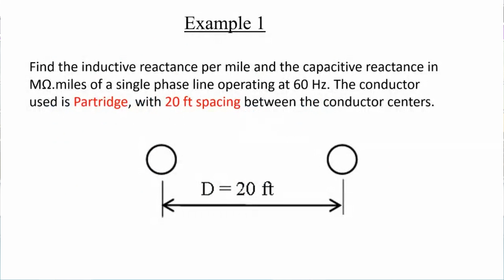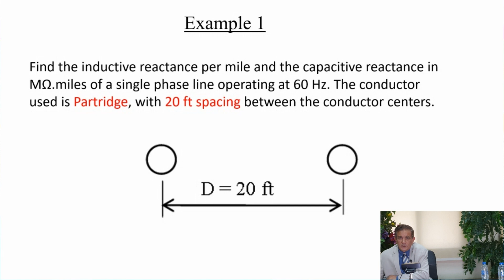For the capacitance, the same thing applies. Maybe this example will explain it: find the inductive reactance per mile and the capacitive reactance in mega ohm miles of a single phase line operating at 60 Hz. The conductor used is partridge, this is the code of the conductor, the conductor name, which will enable you to get the information from the data sheet. They are spaced 20 feet apart.